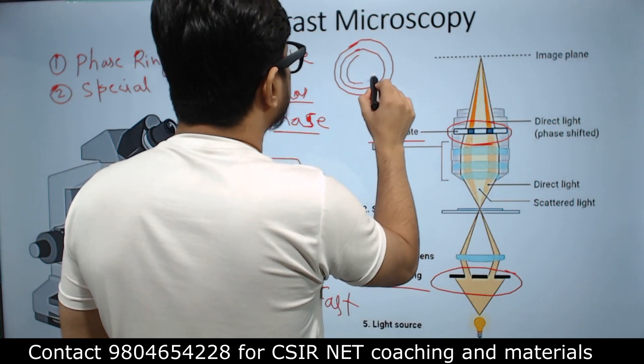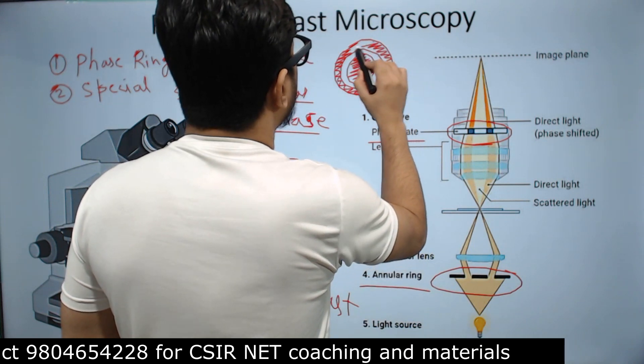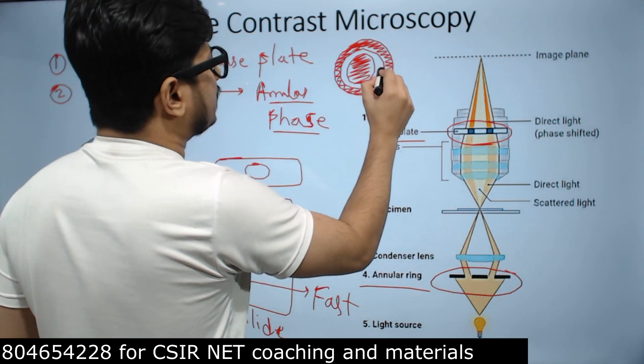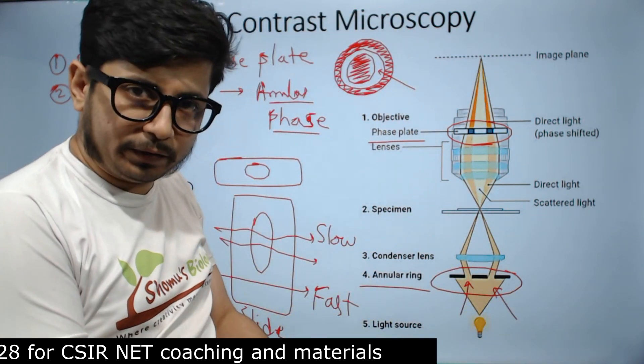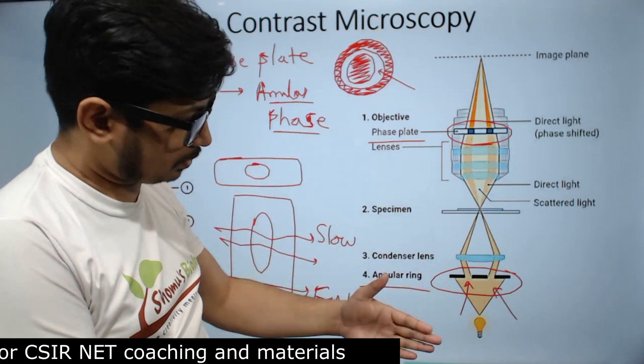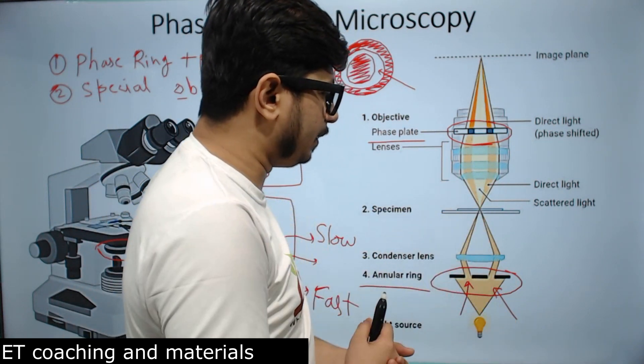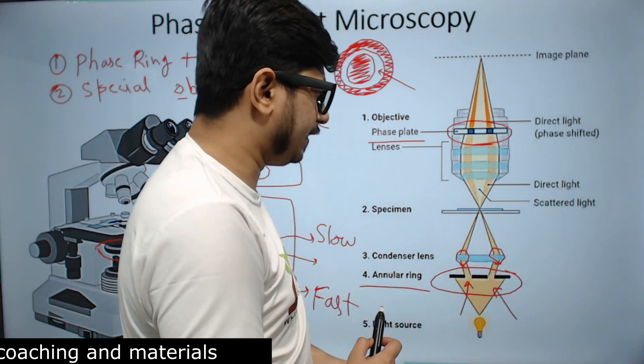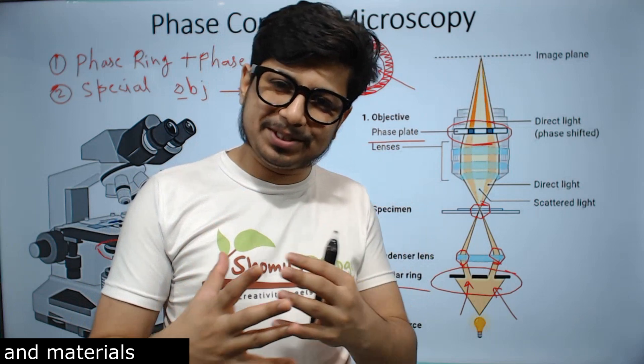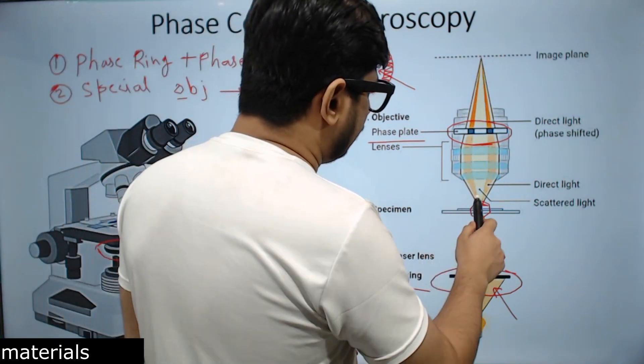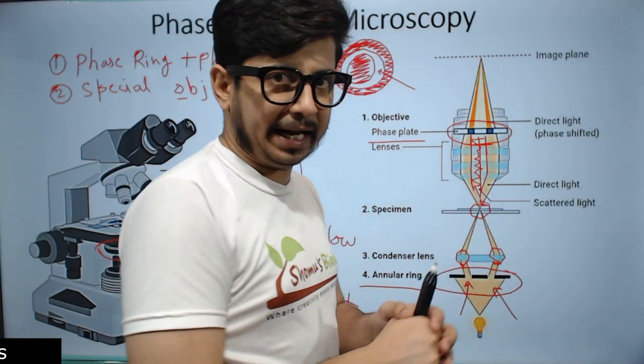The annular ring looks like a disk with a slit opening only at the periphery — the light will only pass from the open peripheral area, not from the shaded area. In a longitudinal section view, these are the points through which light passes. The light only touches the periphery of the condenser and is condensed onto the sample. The sample scatters the light — that is the sample's job. The scattered light from the sample is one component, and the surrounding direct light that passes without scattering from the sample is the other component.